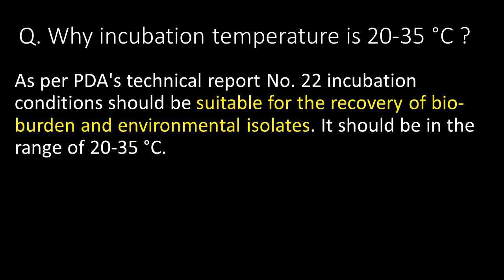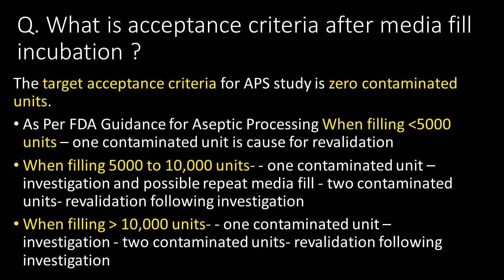Why is the incubation temperature 20 to 35 degrees Celsius? As per PDA Technical Report Number 22, incubation conditions should be suitable for the recovery of bioburden and environmental isolates. It should be in the range of 20 to 35 degrees Celsius.